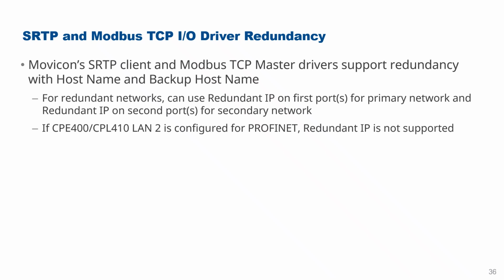But the challenge there is that not every PLC supports redundant IP on the second network if it's also being used for Profinet. So it's a bit harder to do this. So I recommend, where possible, use OPC-UA, but we do have support for redundancy on these legacy networks. And this is also supported in a similar way on other vendors' PLCs, but the other PLCs may not support that redundant IP, so then you just have a single IP address with a backup IP address. So you might need to do a bit of investigation with what your PLC supports if it's not an Emerson PLC.